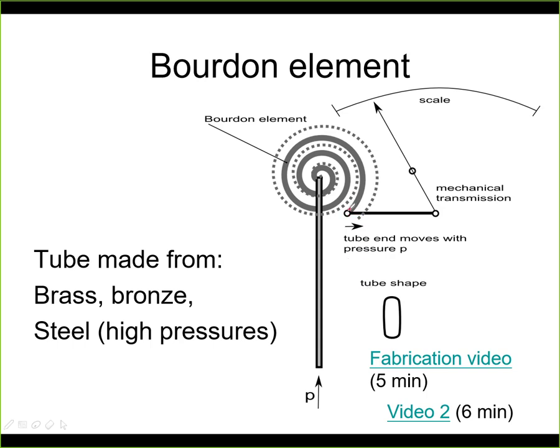At this end the Bourdon tube is closed, and this end is connected mechanically to a system of transmissions. This may be like a lever system. Here you see one lever and a second lever here. It's a simple example. On the next slide we'll see the real instrument. This mechanical transmission changes the motion of the Bourdon tube into the motion of the needle. Here we have the scale, and on the scale we can read the pressure. So the gauge is calibrated in pressure.